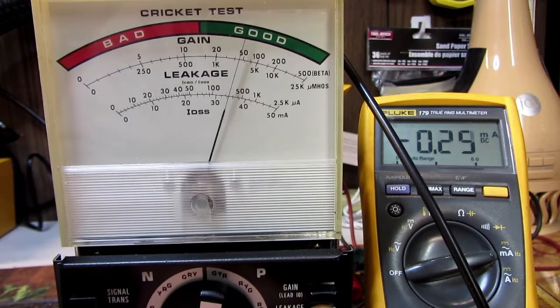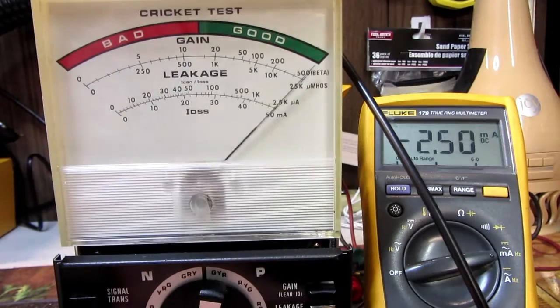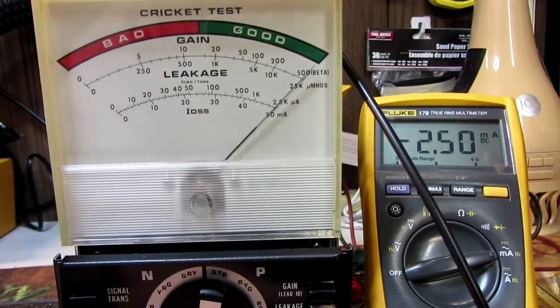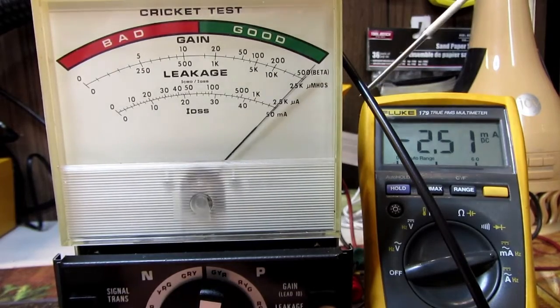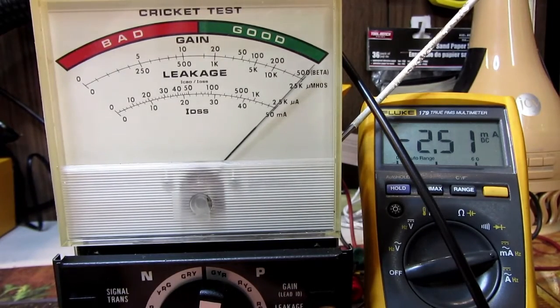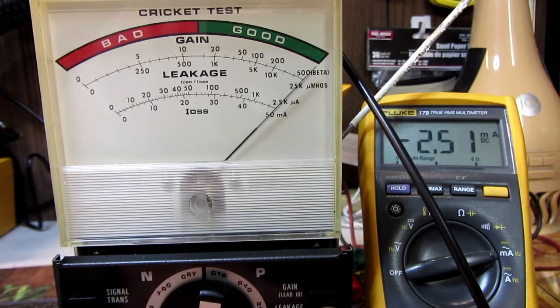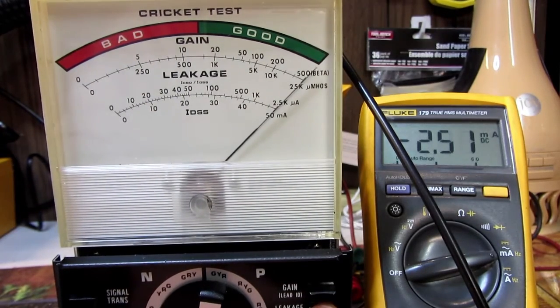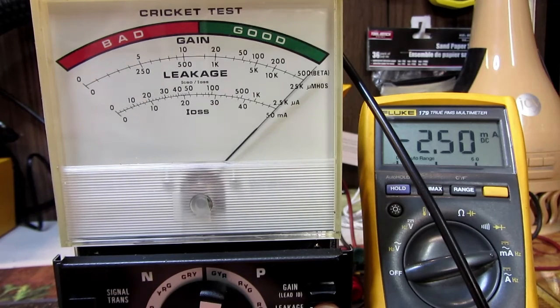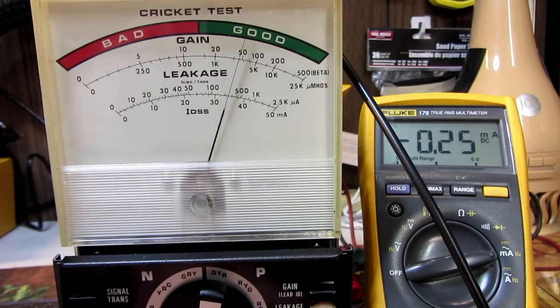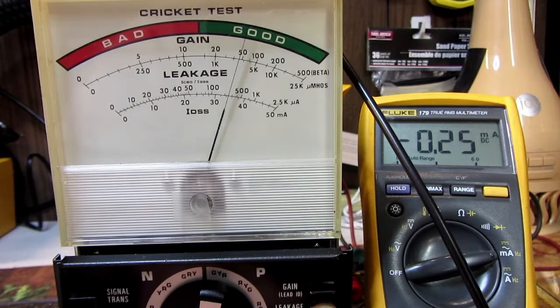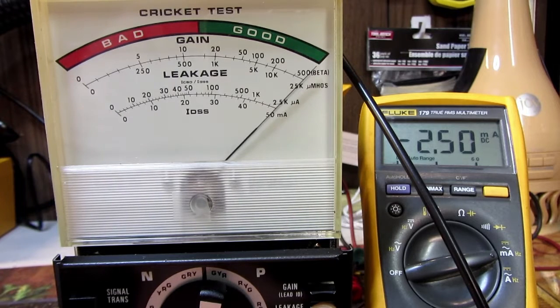Okay, that's dialed in nicely there, so we'll go back and recheck the first calibration point again. Okay, the first range is off just a hair this time. Okay, that's dialed in nicely again, and we'll recheck the other one again. Okay, as you see, we're spot on the calibration now. 250 microamps. We are exactly between the 200 and 300 on the scale. And one more time, we'll check full scale. 2.5 milliamps, full scale. And we have performed the leakage calibration.